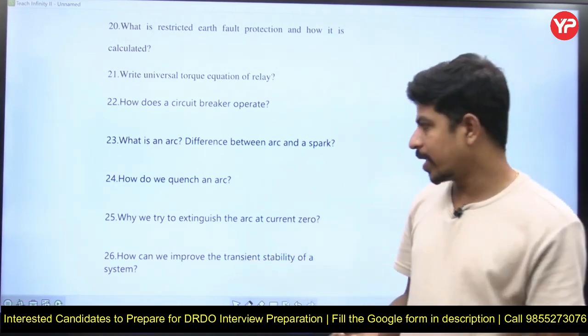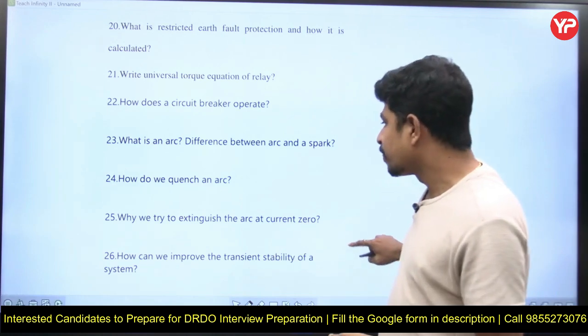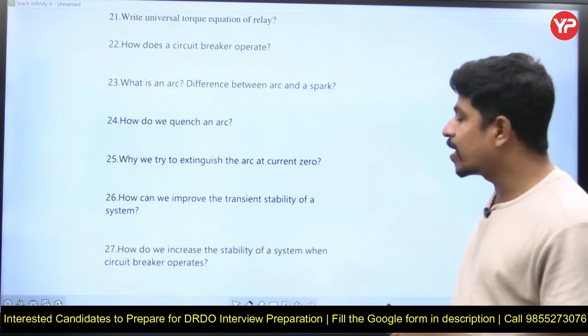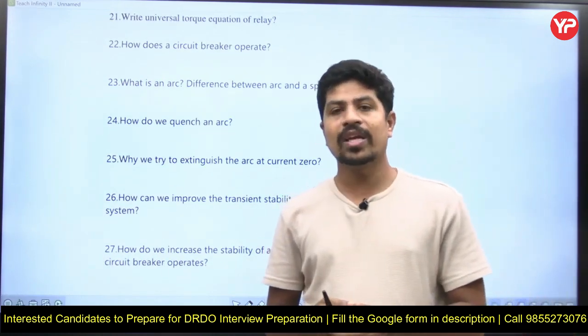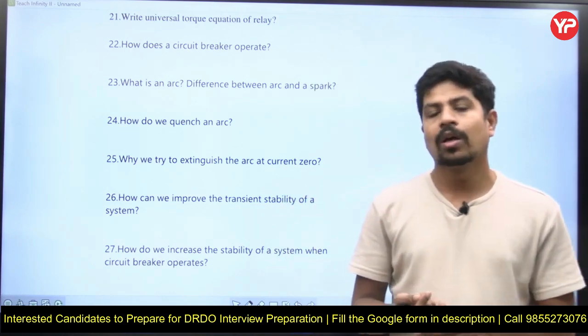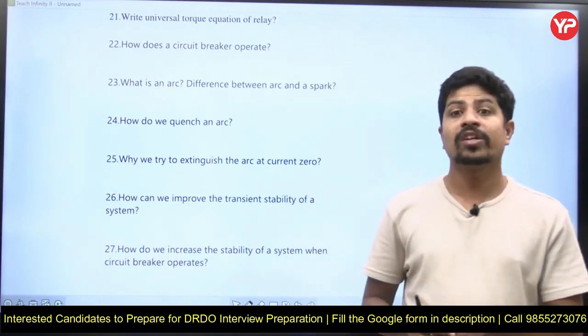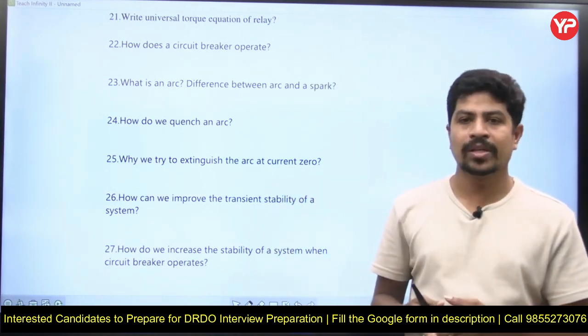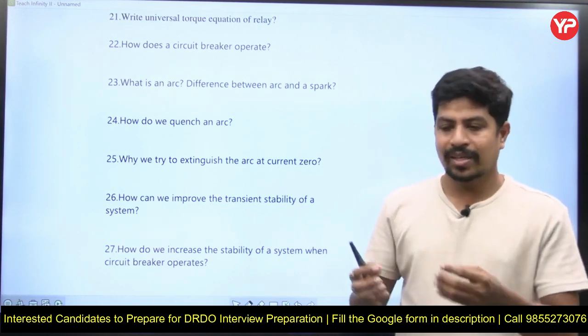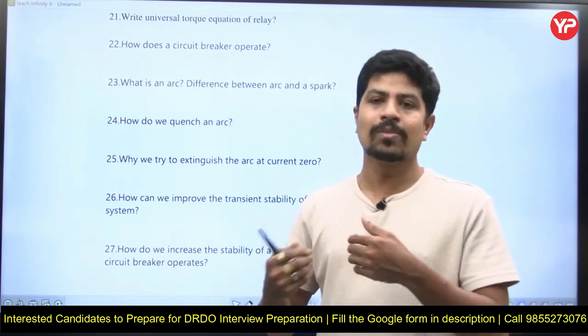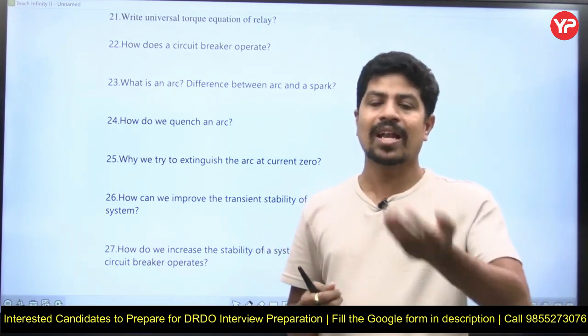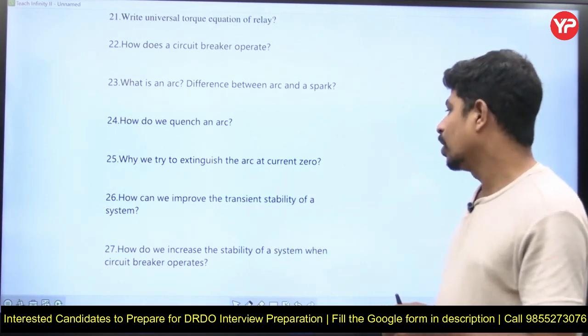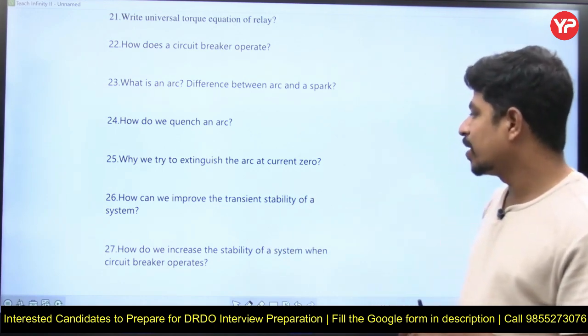How do you quench the arc? There are several methods depending on the type of circuit breaker. Why do we try to extinguish the arc at the current zero point? At the current zero point, the heat energy in the medium is less because heat energy is proportional to I²R, and when current I is zero, the heat energy is minimized — making it the optimal point to extinguish the arc.